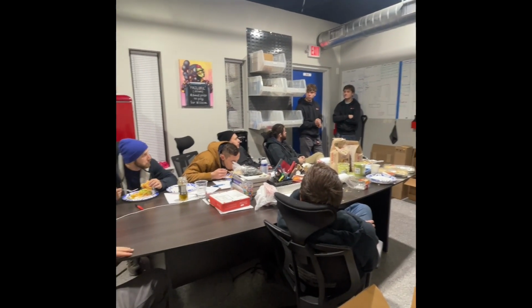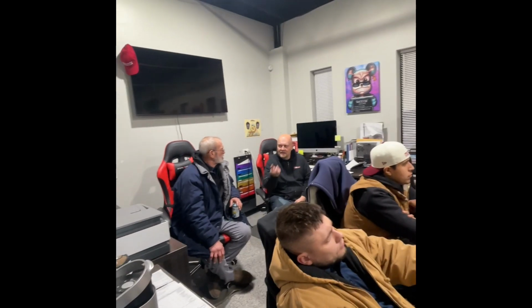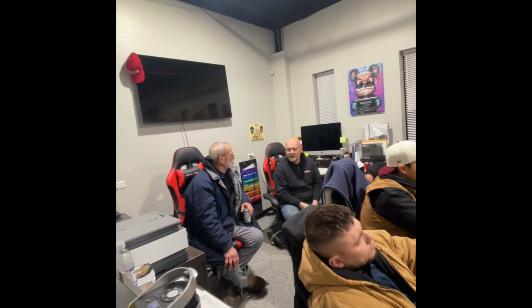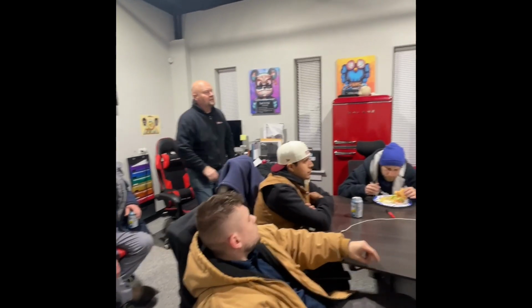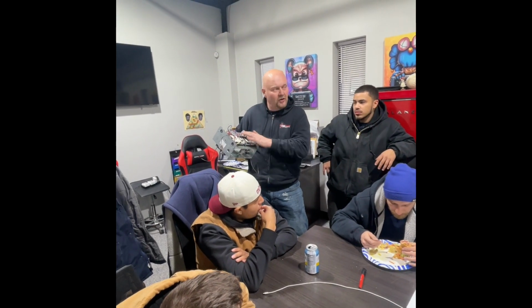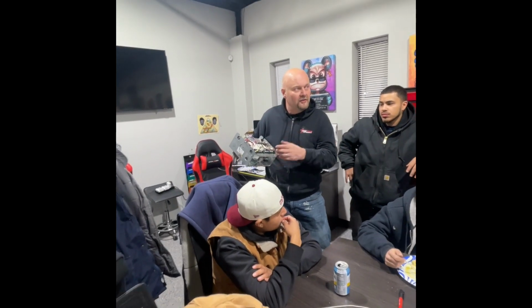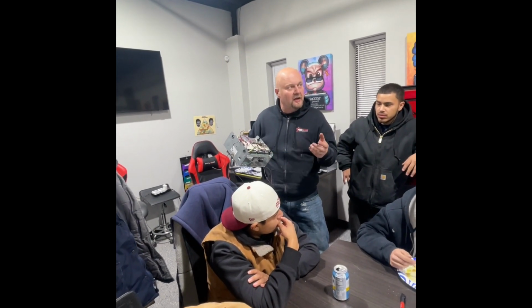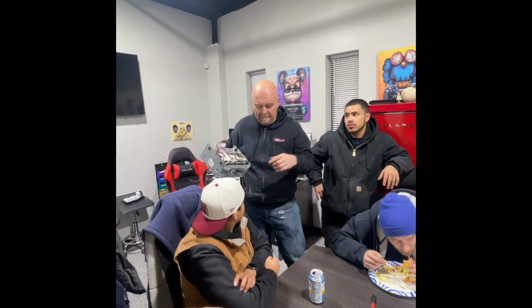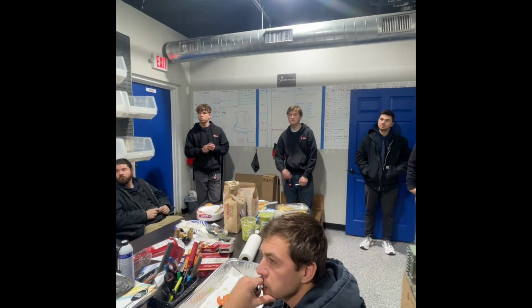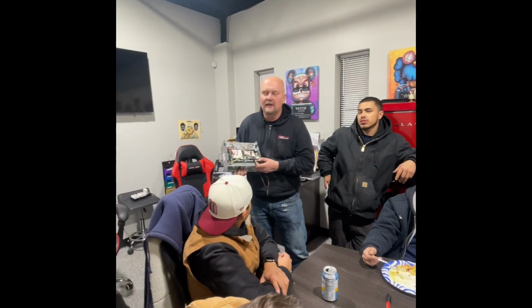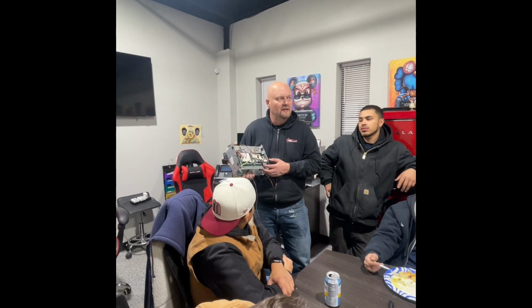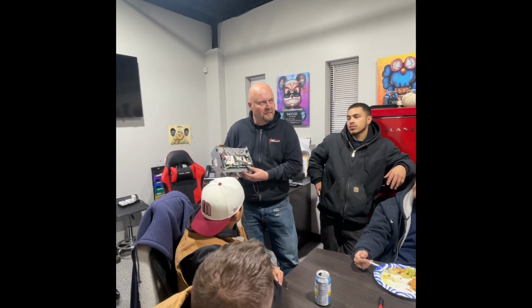Do you guys, anybody have any questions or thoughts? What was the 3rd transformer for the boiler? So the boiler has its own transformer and it sends a signal up to the Unico control board, and there's just an end switch on the hot side. So hydronic hot water, and the bottom of the control board. We had a Unico control board somewhere here, and I wanted to show you guys. Set of contacts. What that means is the control board doesn't send any power to it. All it'll do is close, it can make a connection, or lower the bridge between these 2 contacts. It's basically what we always refer to as a dry set of contacts.